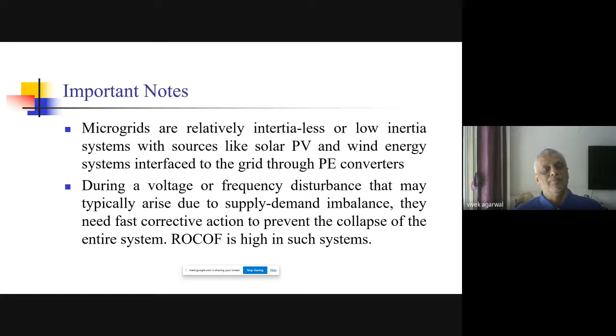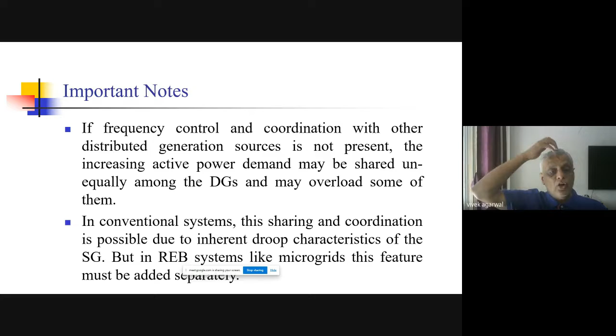So the frequency control and the coordination with other distributed generation sources is not present in a microgrid, all right? The increasing power demand will cause unequal sharing of power among the various DGs, distributed generation sources like the PV and the wind. Some of them might get too overloaded, and some might become too lightly loaded. Some of them may really go bad because of this very unequal and very high power they have to contribute. In conventional systems, this sharing and coordination happens because of the inherent droop characteristics of the synchronous generator. I'm sure there are some people who read about droop control and know what I'm trying to say. In renewable energy based systems such as microgrids, this feature must be added separately.